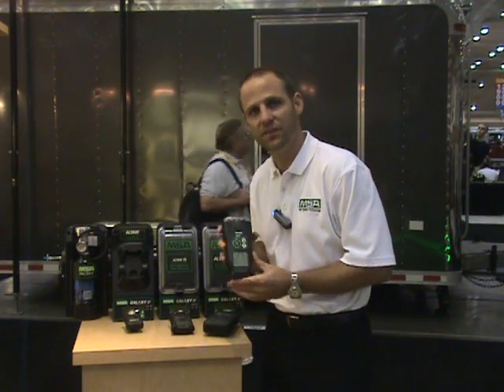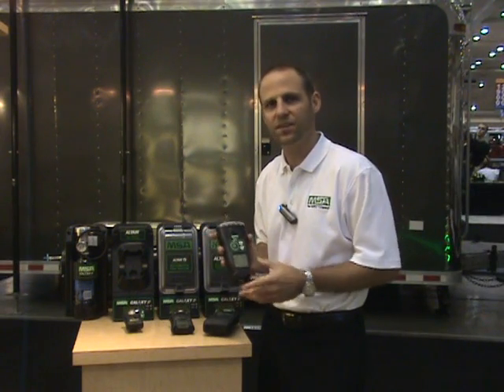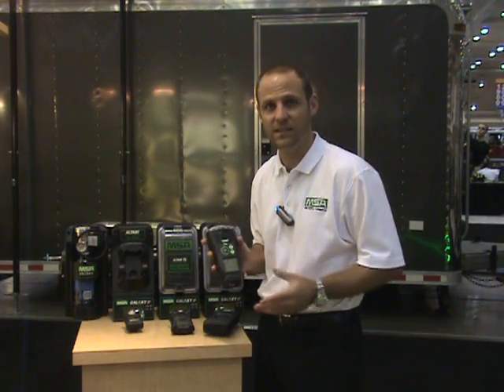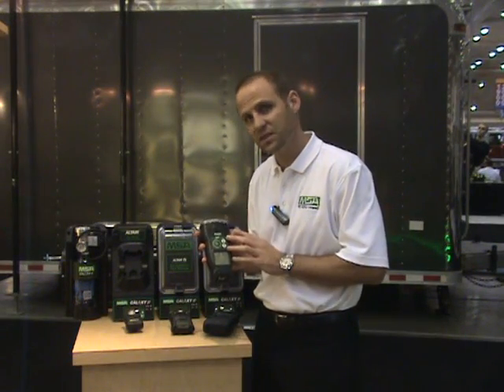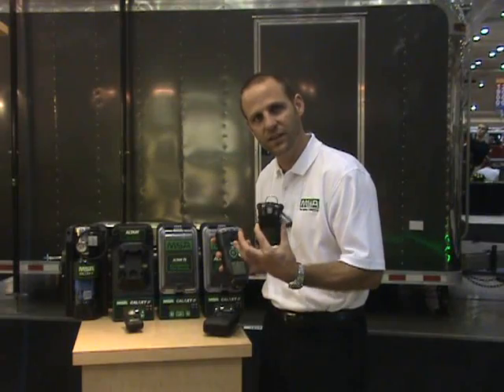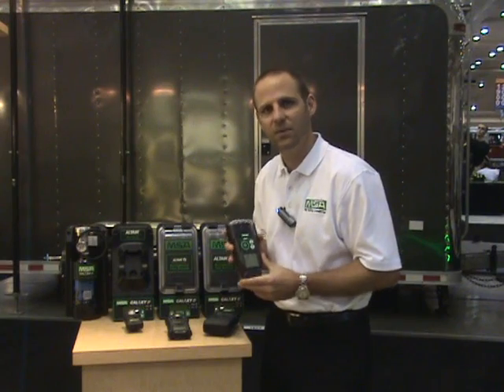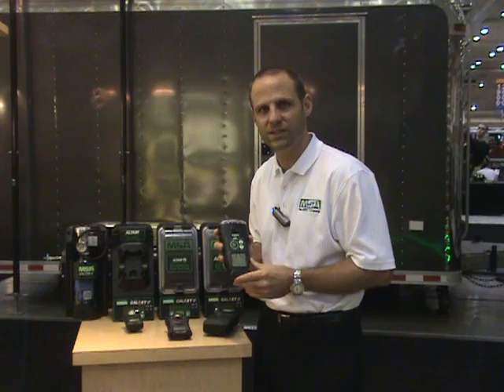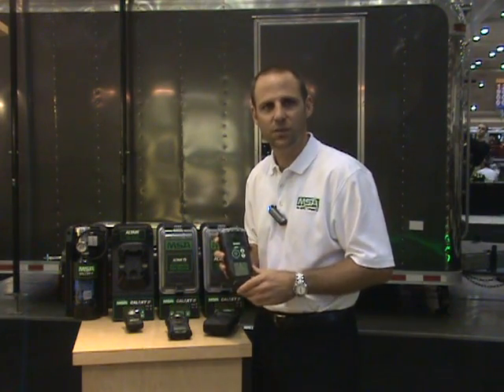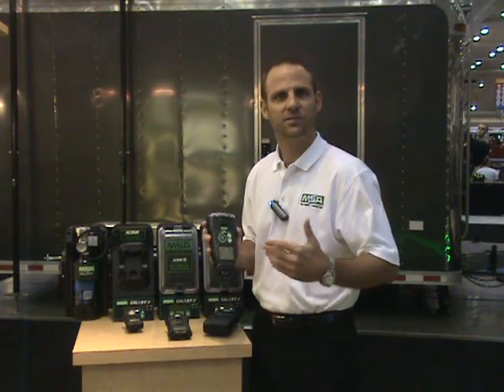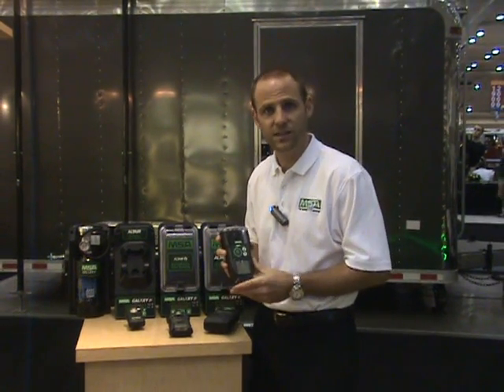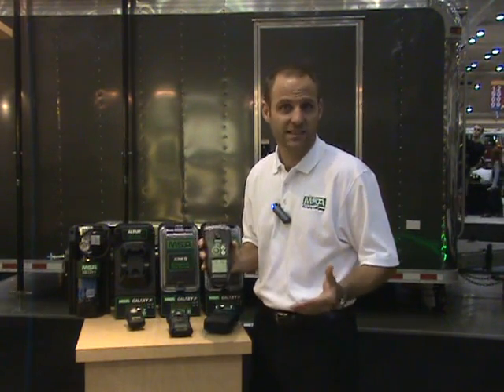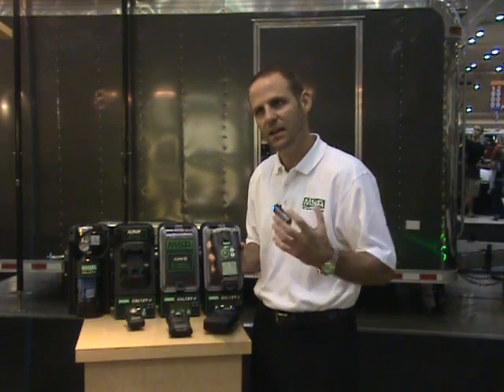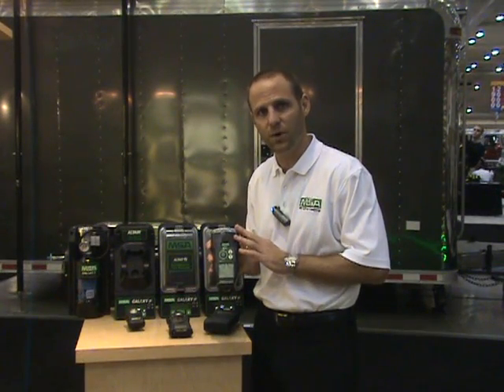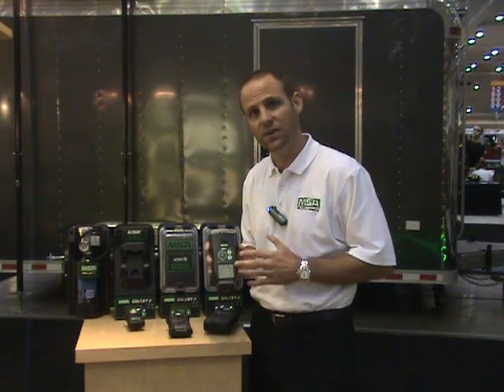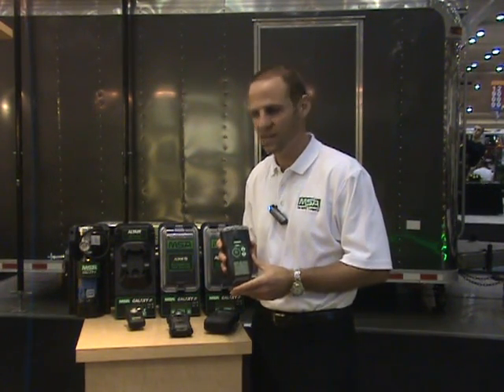So over here, we have the Sirius multi-gas detector. We have literally thousands of these out in the field in use by hazmat teams all over the country. This uses the big 4, so it's essentially you have an Altair 4 built into this unit, and then we also have something called a photoionization detector, a PID. What that does is looks for volatile organic compounds, anything from accelerants that might be used in an arson case, to floor cleaners, to gasoline or aviation fuels. Anything that's volatile and organic, this will look for it. It'll give you a sense of how much is there if you know what you're looking for, and it's a great tool used for hazmat.